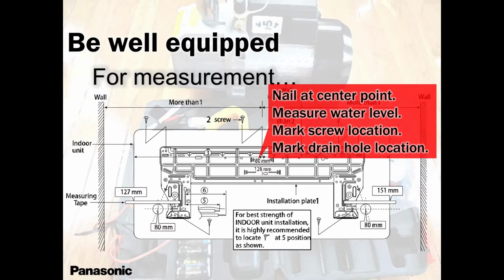So please always remember that if it's a very high job, like in a high-rise building, and the indoor unit is on the second, third floor, and the outdoor unit is all the way down, please make your connections inside. Exit from the left-hand side, not from the right, okay?